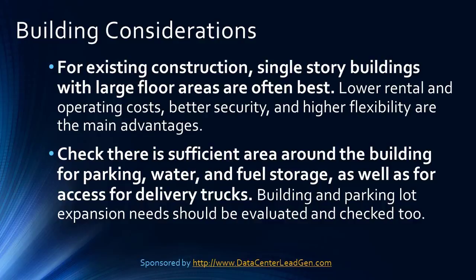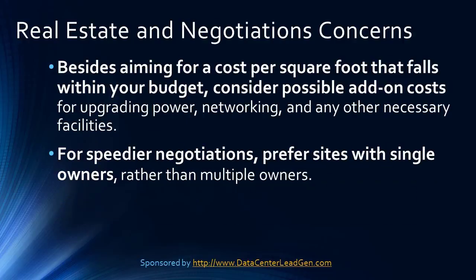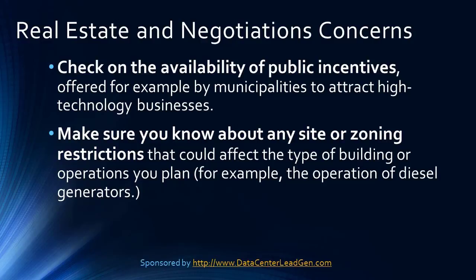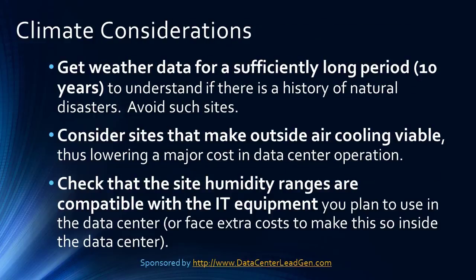Building and parking lot expansion needs should be evaluated and checked too. Real Estate and Negotiations: The cost of real estate and negotiations can be showstoppers. Besides aiming for a cost per square foot that falls within your budget, consider possible add-on costs for upgrading power, networking, and any other necessary facilities. For speedier negotiations, prefer sites with single owners rather than multiple owners. Check on the availability of public incentives offered by municipalities to attract high-technology businesses. Make sure you know about any site or zoning restrictions that could affect the type of building or operations you plan, for example the operation of diesel generators.